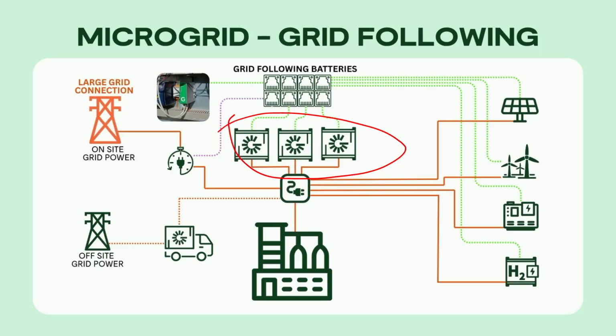This is the same technology we use for our microgrid as well, to balance all the energies out. If we try to use our microgrid technology while we have the national grid connected, that won't work. That's why, when our microgrid is connected to the main national grid, we use a grid following mode - you pick the strongest thing within your assets to be in control of that frequency, which would be the national grid.